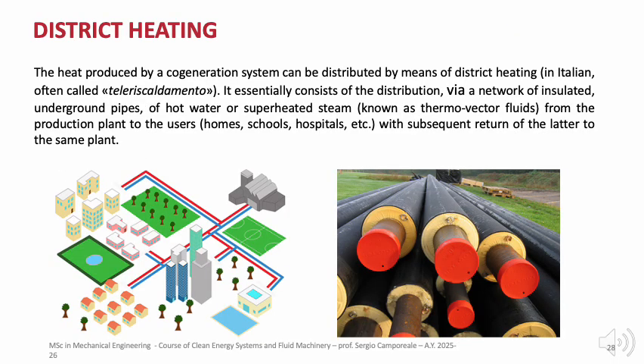One of the most effective ways to exploit the thermal energy produced by a cogeneration system is district heating. Rather than using the recovered heat only locally, district heating allows this heat to be distributed to a large number of users through a dedicated network. This network consists of insulated underground pipes that carry a thermal vector fluid, typically hot water, superheated water, or steam, from a central production plant to the end users. Typical users include residential buildings, schools, hospitals, and other public or commercial facilities.